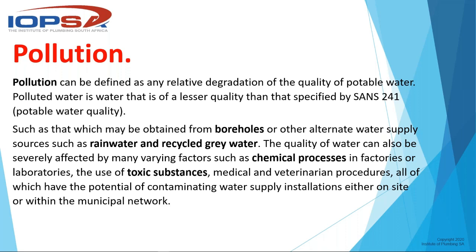Regarding pollution, water which may be obtained from boreholes or other alternative water supply sources such as rainwater and recycled greywater is considered polluted. We may understand why rainwater and recycled greywater — because there could be toxins, acid rain, bird droppings in the rainwater. But often boreholes are also much cleaner than even the municipal line. It doesn't matter — unless it's been regularly tested, you are not allowed to have it flow back. It's got to be specified and tested to SANS 241.